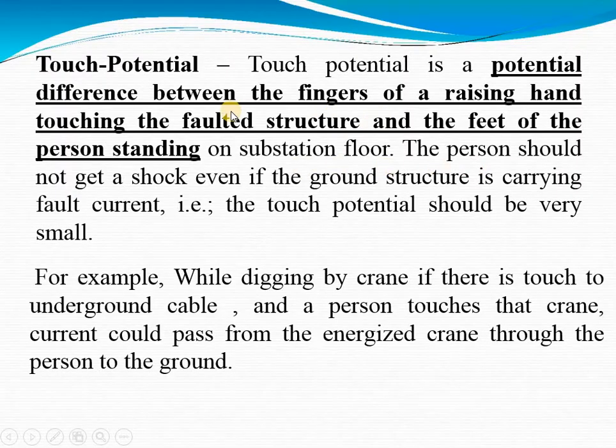The definition of touch potential is the potential difference between the fingers of a raised hand touching the faulted structure and the feet of the person standing on the substation floor. The person should not get a shock even if the ground structure is carrying fault current, so the touch potential should be very small.